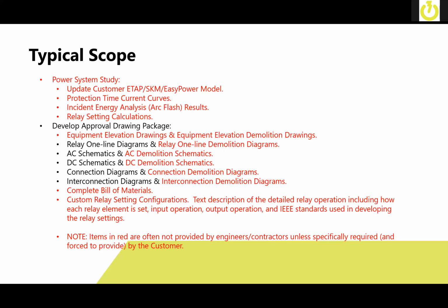A lot of times if you call someone out of the blue, a lot of these items aren't provided. It's typically a limited approval drawing package just showing what was installed, which can lead to issues when you go out in the field and try to start demolishing it, and maybe it doesn't match what you expected to see. Or if you get a third-party contractor to do the installation and they start trying to demolish and it doesn't match what they're expected to do.